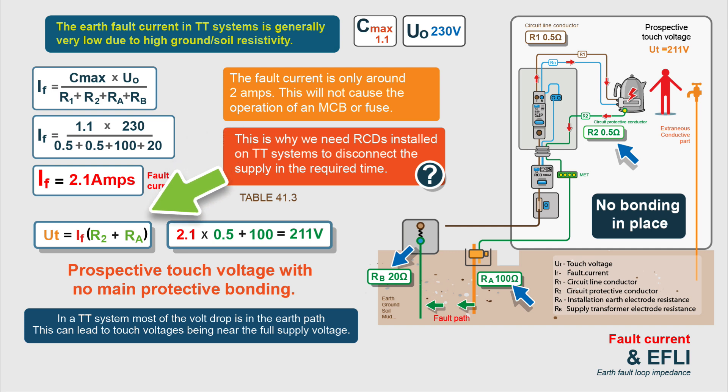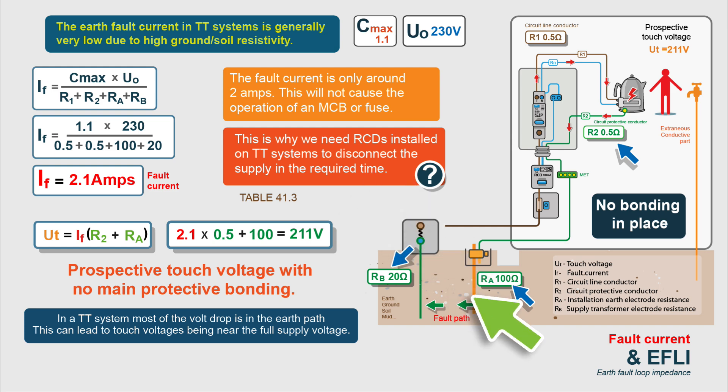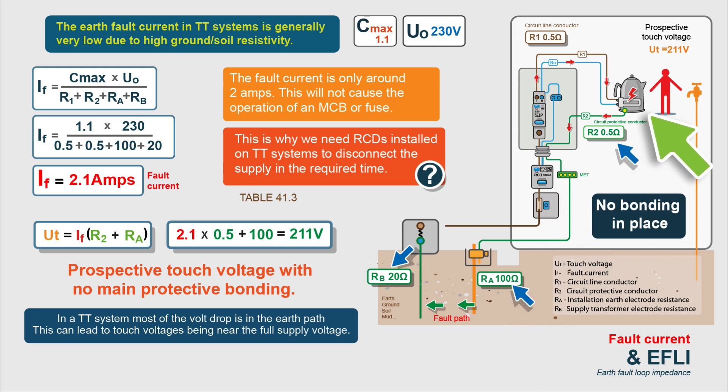So now we can calculate our touch voltage — and this is the touch voltage with no bonding in place. Touch voltage is the voltage that can appear on exposed or extraneous conductive parts during a fault. The formula is: UT equals fault current times (R2 plus RA). Doing the maths: 2.1 times (0.5 plus 100) equals 211 volts. That is a very high touch voltage. The reason for this high touch voltage is that most of the volt drop is in the earth return path, giving us a very high touch voltage at the fault.